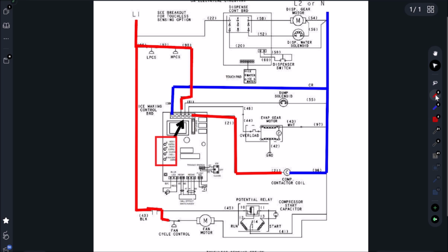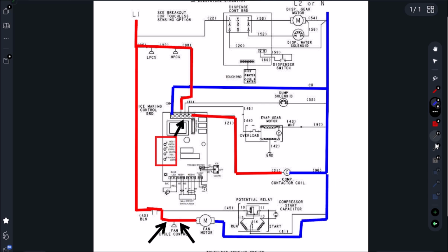Now the second thing I did was I tested potential difference from here to here. So I have 120 volts in, I had 0 volts across. What is that telling us? That's telling us this switch is closed. So my fan cycle control is doing its job. Okay, now we have a complete circuit. So that's telling me one or two things are happening here. Our high pressure cutout switch is opening before 450 psi, or this fan motor is not running.